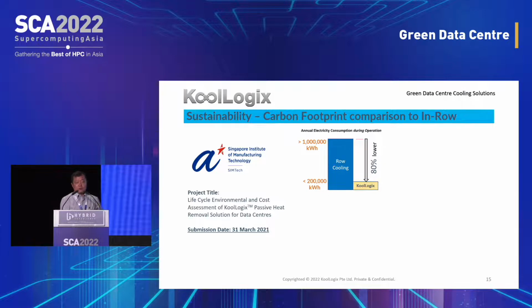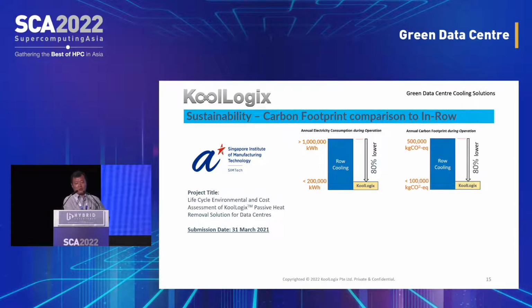Breaking it down further: during operation, compared to in-row cooling, KoolLogix has an opportunity to reduce power consumption by as much as 80%. Overall it's 50%, but during operation—so OPEX cost saving—for cooling solution power consumption alone, we have 80% lower power consumption, which translates to an 80% reduction in carbon footprint without going through any sophisticated analysis.